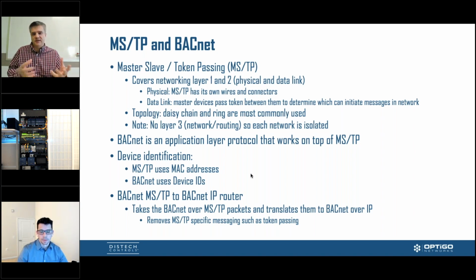Typically, this is mostly used in a daisy chain or a ring format, not typically in a home run. It doesn't make any sense. One thing of note is it doesn't really have a layer 3, which is where the routing comes in and where you can connect different networks together. So usually MSTP networks are isolated.